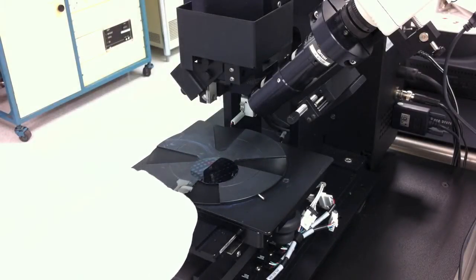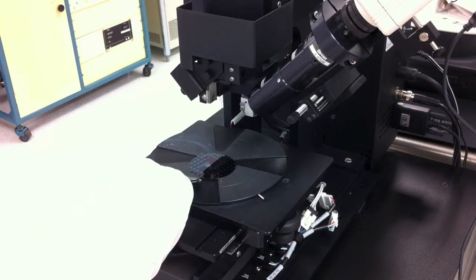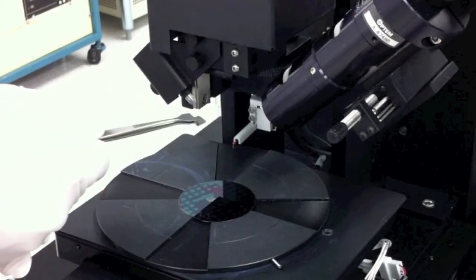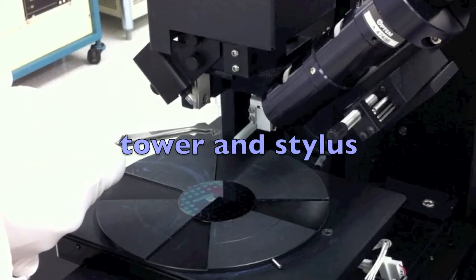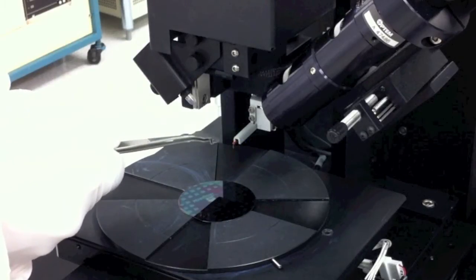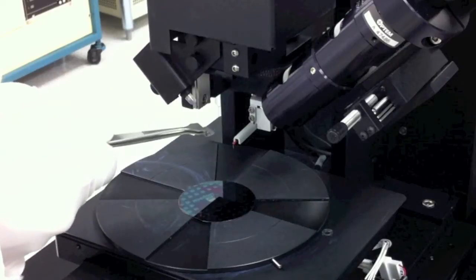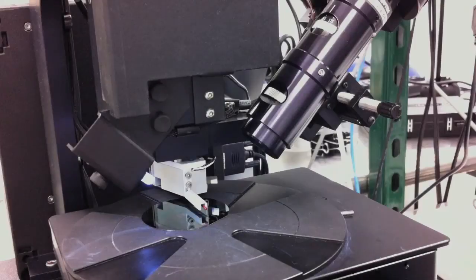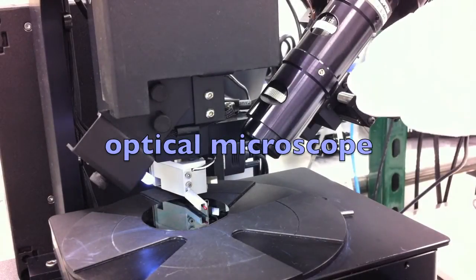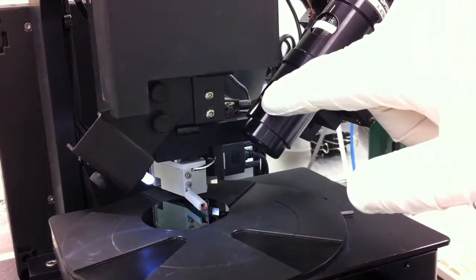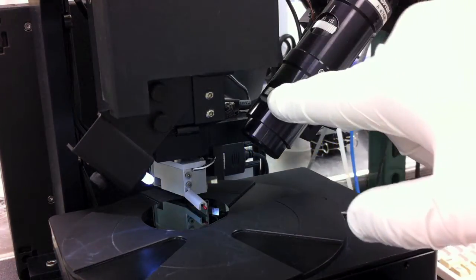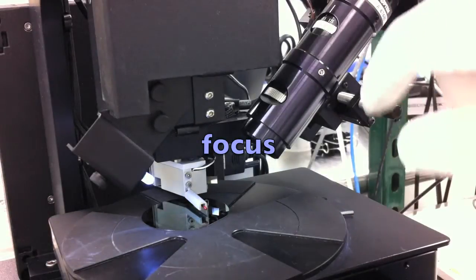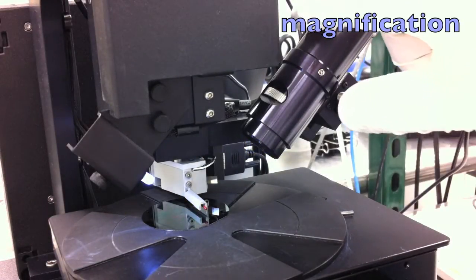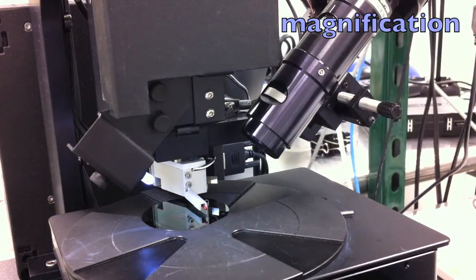And besides surface topography, sample roughness and film stress can also be calculated from several scans of different areas within a sample. Here we can just make out the tower and the stylus. The tower is used to lower the stylus until the tip makes contact with the sample below. To the right is an optical microscope, which is used to help the user align the probe tip with a particular feature of interest. The first dial changes the focus of our image, and this second dial can change the magnification power for the microscope.